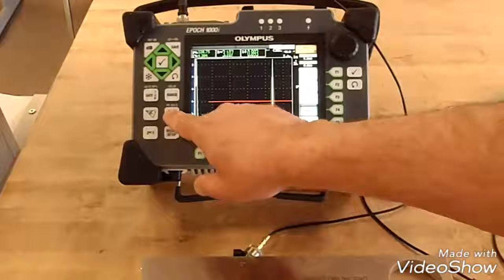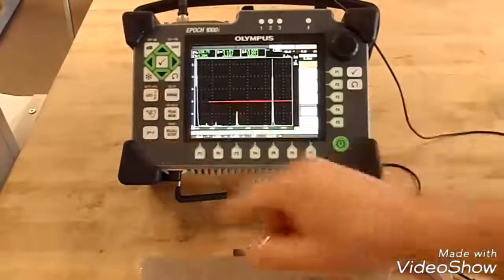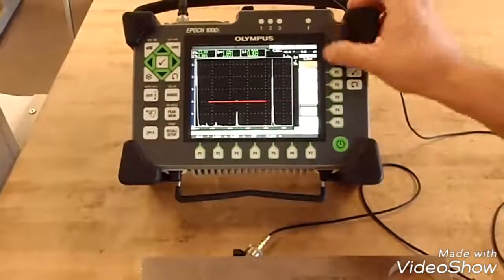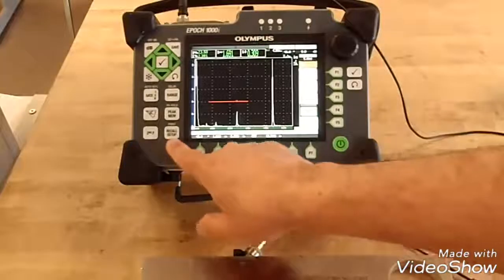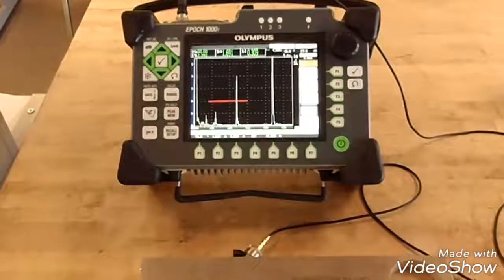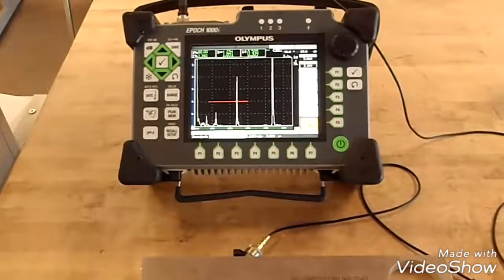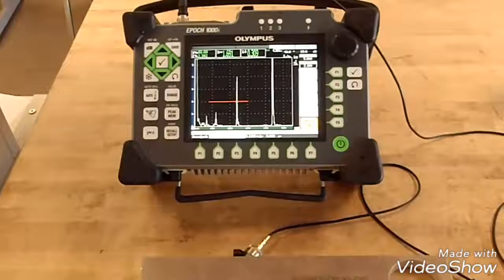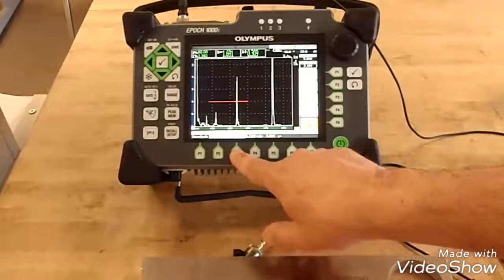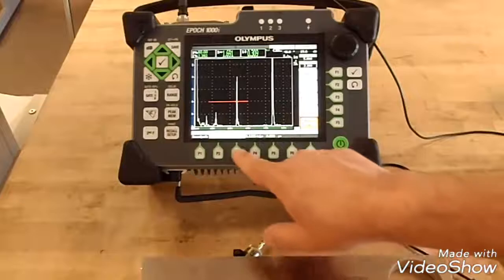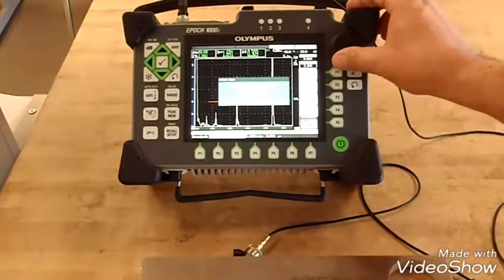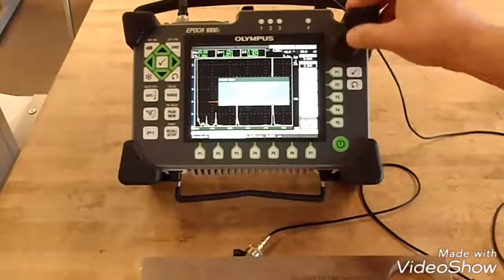I'm going to take my gate and turn down the width so it'll just capture that two inch radius. Do second function auto 80. This will take your amplitude to 80% full screen height. Go to auto cal. The first thing you want to do is calibrate your zero. You're going to tell the system from an initial pulse to that first two inch radius that it's two inches. That's called calibrating your zero.